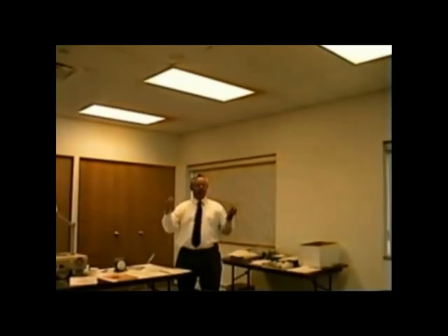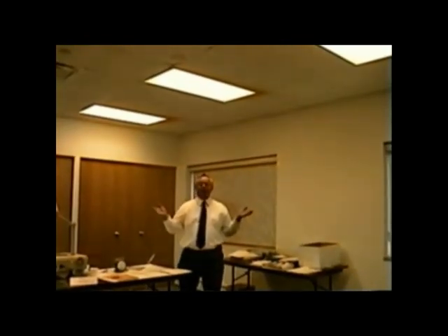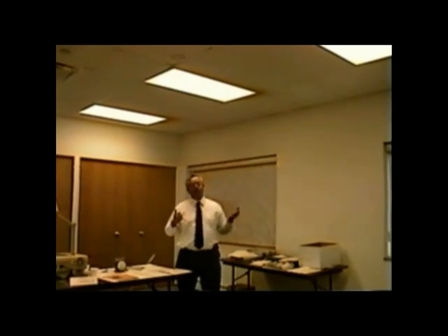Out of 31 questions on an 80 plus furnace, we didn't use 8. So what does that leave us? 8 from 31 is 23, right? Those 23 questions. But hey, even if you're doing a 90 plus, it's all the same information, all the same diagnostics. The only thing that's different with a 90 plus is to talk about your venting. This is how you diagnose in 20 minutes.